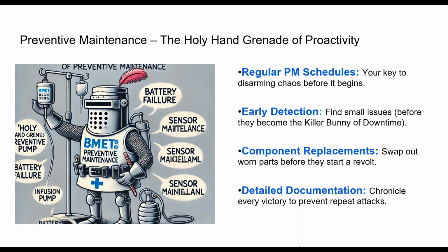And detail your documentation - I say this with a grain of salt. Many organizations will take the road of, if the manufacturer says simply check off a box that says passed for the overall PM, then that's sufficient. I will tell you personally, before you move to an AEM strategy, it's important to document what the manufacturer recommends and not document anything else on the preventative maintenance. On a repair, make sure you're documenting something that clearly reminds you and communicates to other people what the real problem was and what your resolution was.